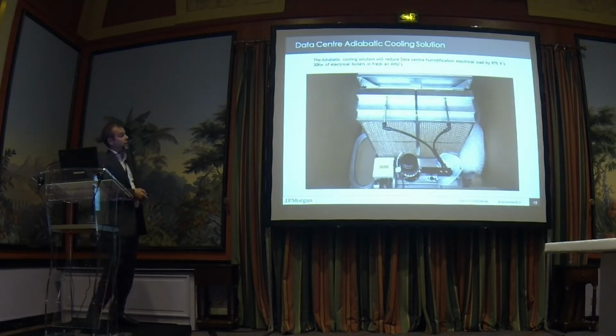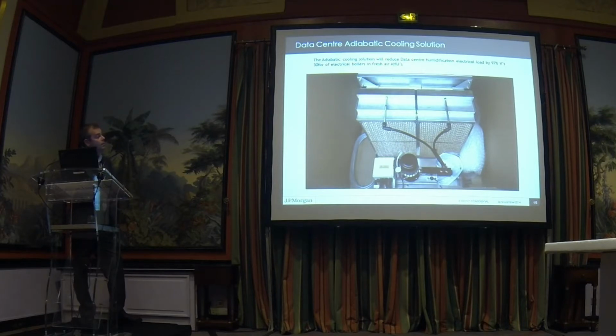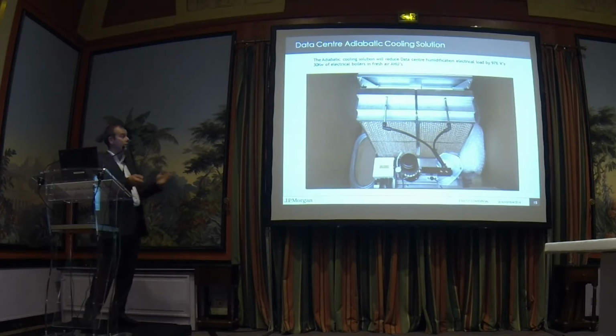So this is the adiabatic solution. This is like a wood pulp matrix in there. You've got a little pump and you've got two sprayers in there, and that's the duty control on it. If you need 50%, one turns on, the other one turns on, you're 100. The bigger these are, they've got more pipes hanging off them. You can see down there, there's like 5 connections there. So I can extend that thing that way and have more stages on it.